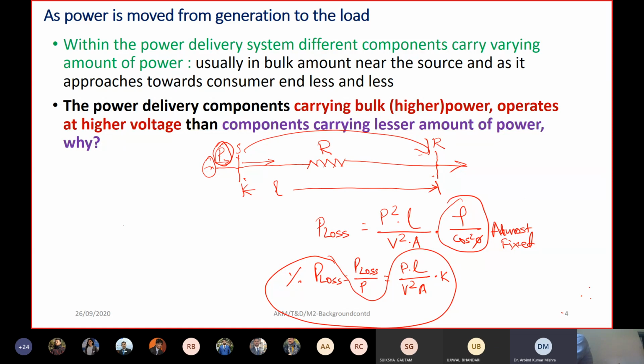So what does this mean? If everything else remains the same — same voltage everywhere, same conductor size and material — then if you have 10% loss for 10 megawatt transmitted over 10 kilometers, for 100 megawatt over the same 10 kilometers, the losses will be multiplied by 10 times, that is 100%. So the loss will be much higher.